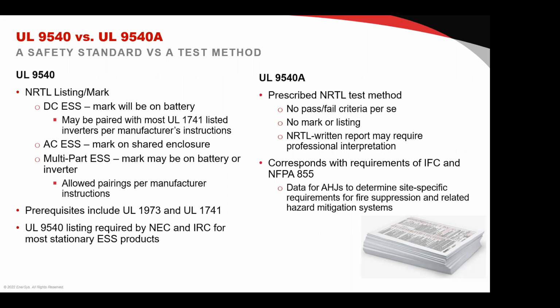For example, part of the test that they do for lithium batteries is they wrap the cells in a thermal blanket that will heat up and force a thermal runaway condition. And then they look at adjacent cells and see if that thermal runaway propagated to adjacent cells. That's one test that they do. They also test and see if any flammable gases are emitted during this forced thermal runaway test. So they look at that test result and say, oh yeah, the thermal runaway did not propagate to adjacent cells, or just a couple. There's no gas being emitted, then it's probably not going to require anything. They'll probably just say, okay, we can go ahead and go forward.